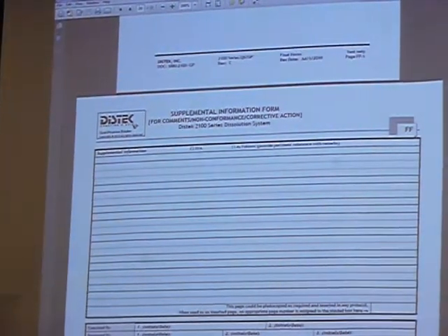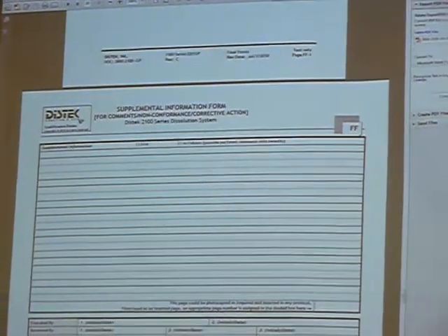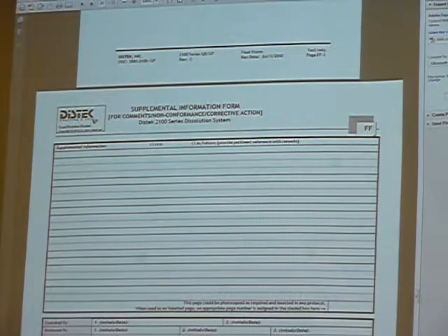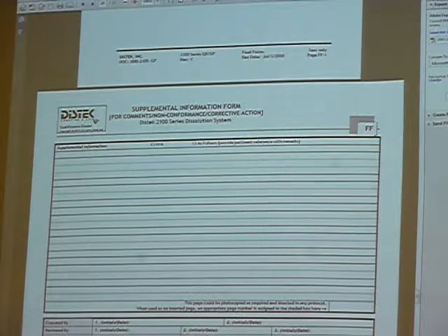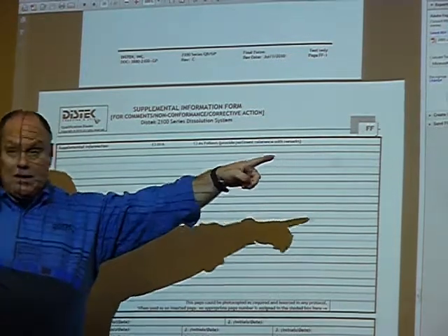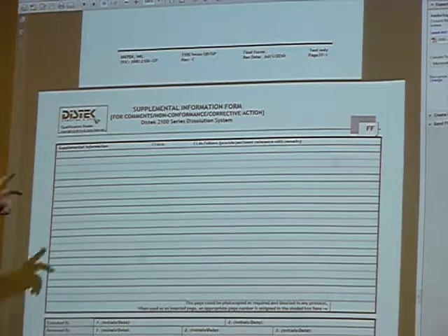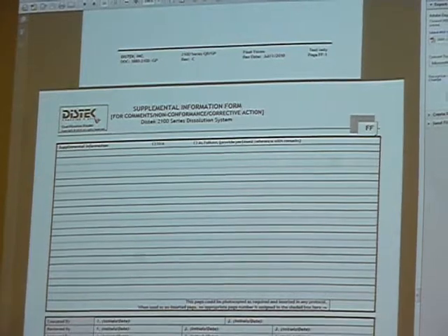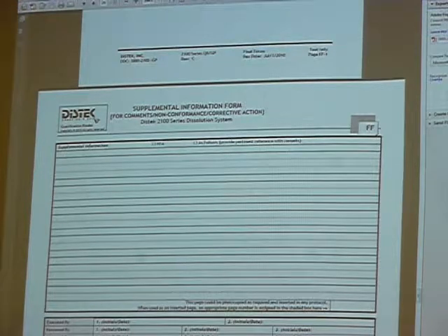I don't know if you guys are familiar with that, have you encountered that at all? It's a shortcoming in our engineering department not communicating to the service department the changes they were making in the document, or I should say with the firmware. And because they did that, I now have to rewrite the document, because the document doesn't cover that. So right now, you have to write an amendment, or write down in the corrective action area how you're going to do the testing. Actually, you could measure for 2 minutes if you want to. You can simply measure it and make sure that it runs at least for a minute for the RPM. I think it counts down after 1 minute, correct? Yeah. Doesn't it run for 1 minute and then you get a timer that counts down after the 1 minute?